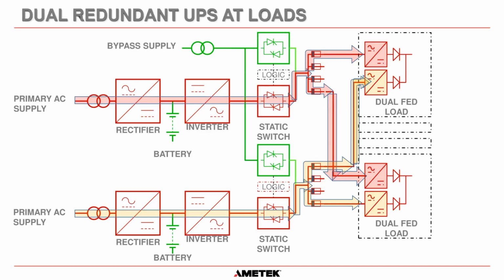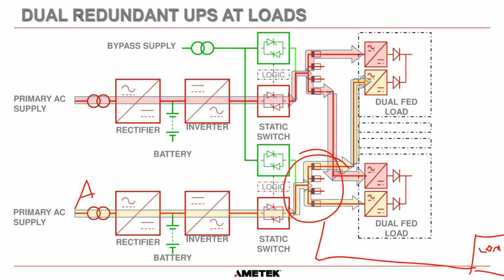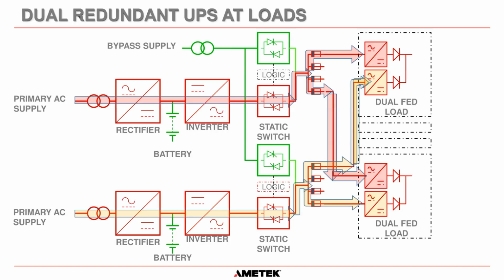And what I've seen historically is when there is a project that comes up and they say, oh, I need UPS power, then they'll look at the drawing and say, okay, let's take UPS power from the UPS A distribution board here, and they'll run it down to a different load out here. And they won't connect UPS B to that load. They'll forget about that. And then when you do that, you don't have the redundancy anymore. Yes, that load will still be backed up by a UPS, but it won't have parallel redundancy. So always be careful when you have this kind of UPS. When you're adding additional load after the systems are installed, maybe a few years from the time they were installed, you have to remember to add both feeds to that additional load that you have added.